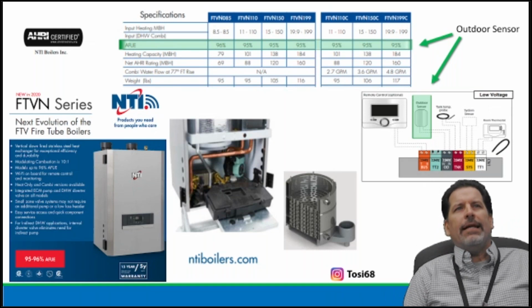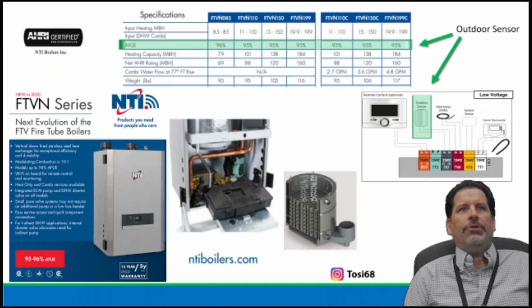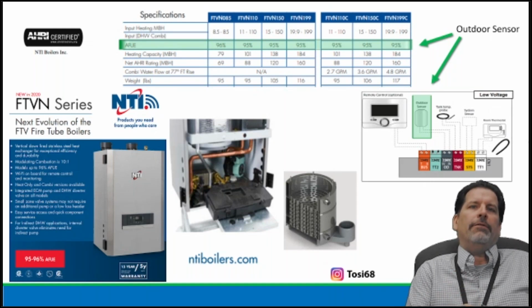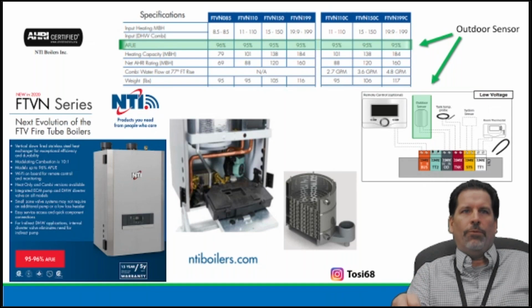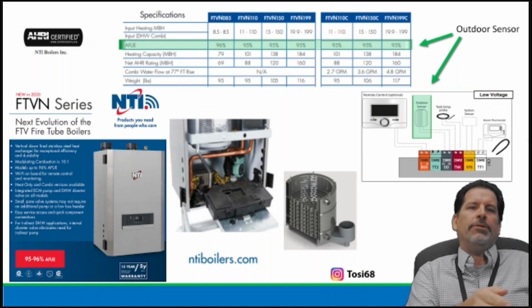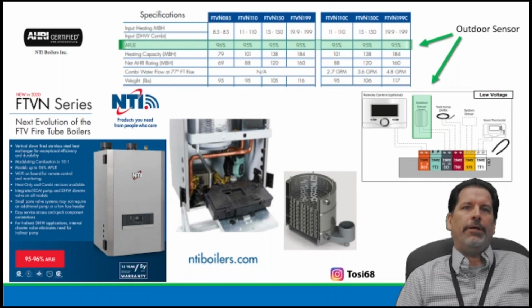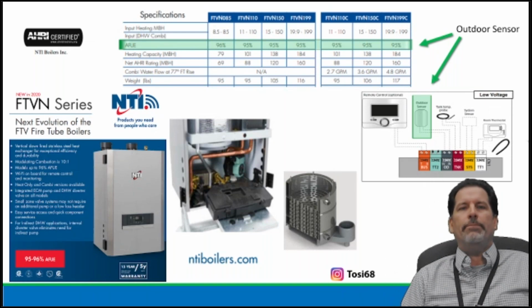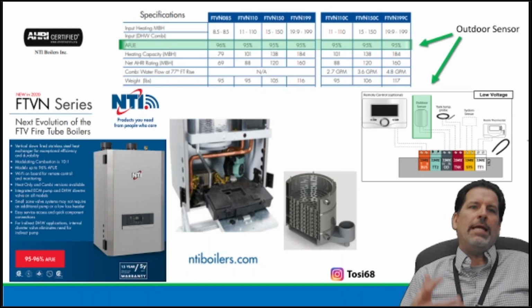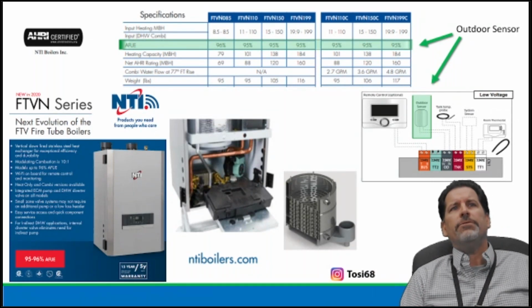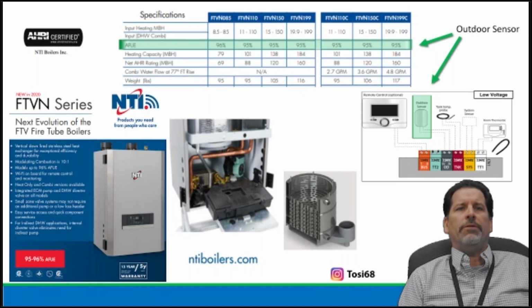but that FTVN085, it says it's an 85,000, right? And it says 8.5. I don't know if the decimal point comes out clear on the screen, but that's a 10-to-1 turn down. That's the beauty of outdoor sensor, right? I only need to deliver for the worst day of the winter, or worst night of the winter. And as that temperature gets warmer out, I'm seeing the change in temperature. So now I can shift based off of the reset ratio. Now my burner can change. The blower RPM is what is pulling the gas through the gas valve, right? And that's how we fire it off. So everything is based off of performance of outdoor reset.